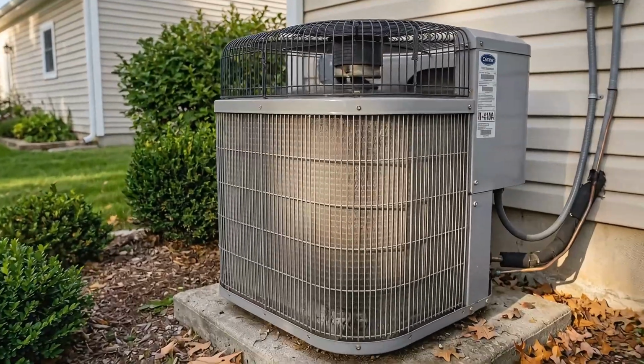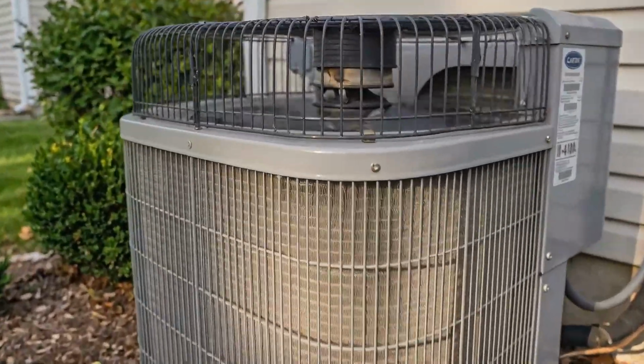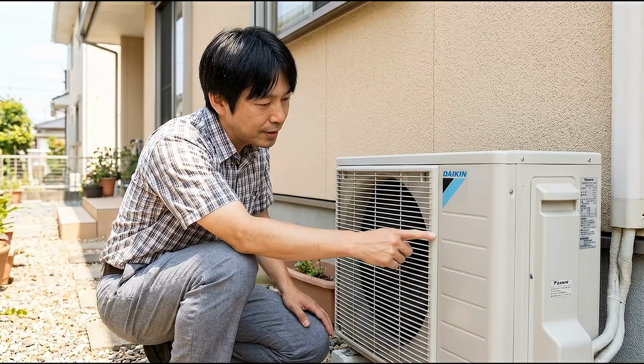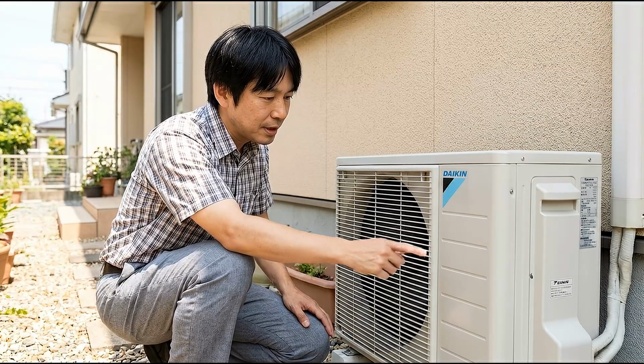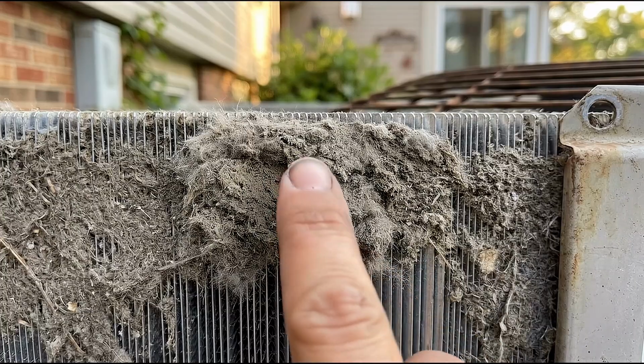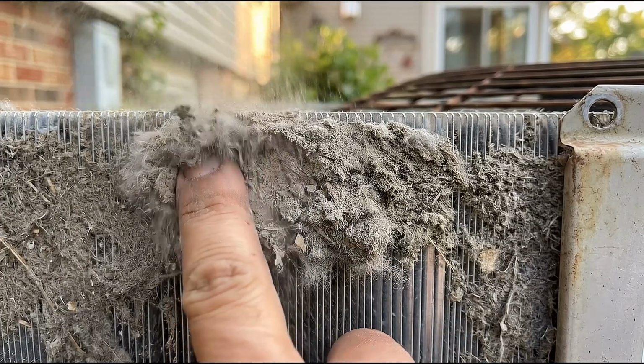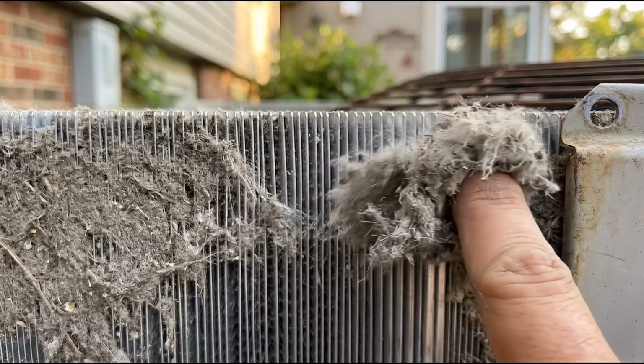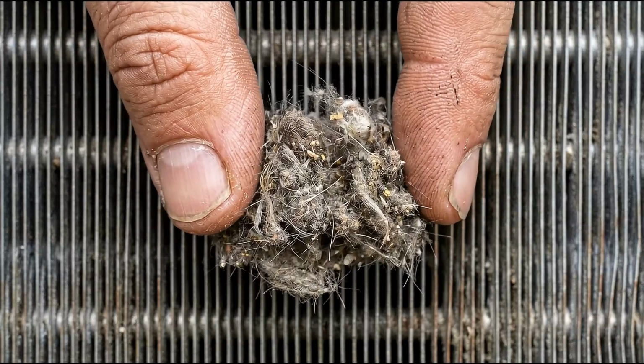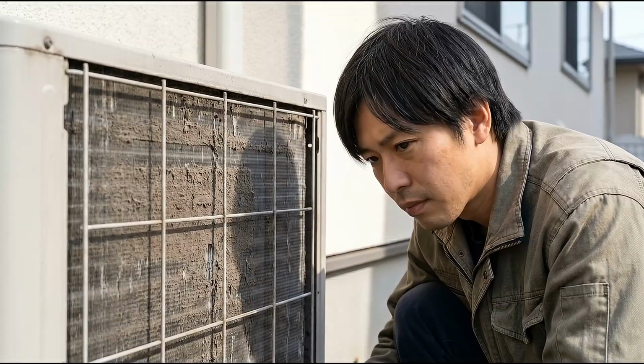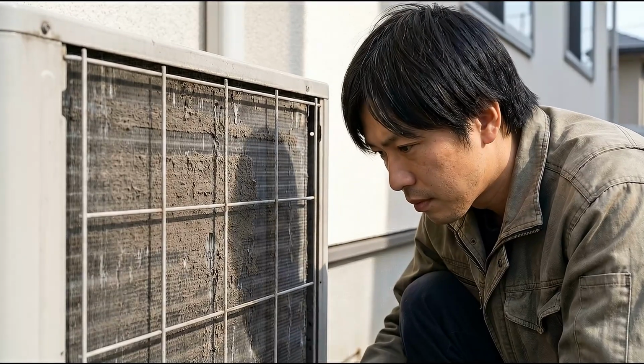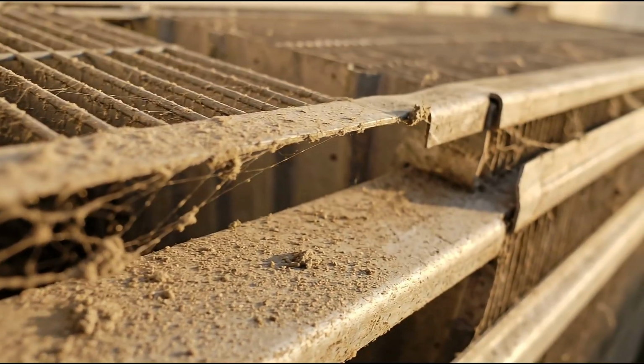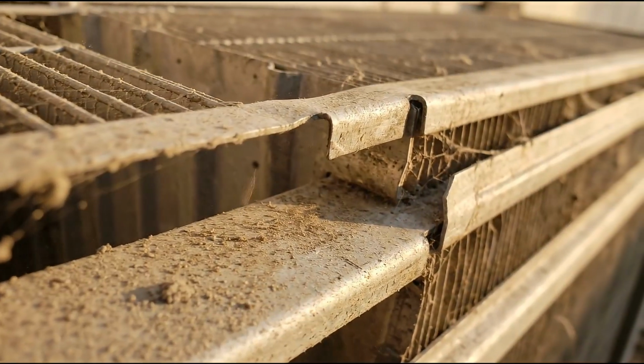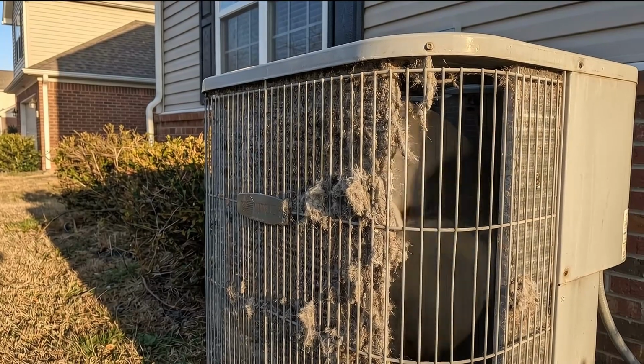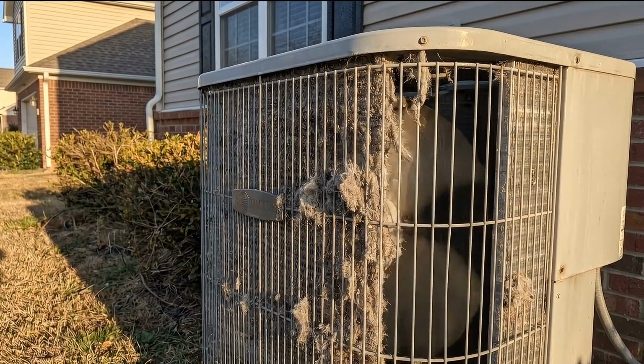Look at that condenser coil, the one sitting outside your house right now. If you walked out there and ran your finger along those aluminum fins, you would probably pull back a pad of grey felt, matted dust and pollen, and cottonwood seed packed so tight it looks like dryer lint. According to the EPA, a layer of that grime just 0.042 inches thick, about 1/23 of an inch, causes a 21% drop in your system's cooling efficiency.